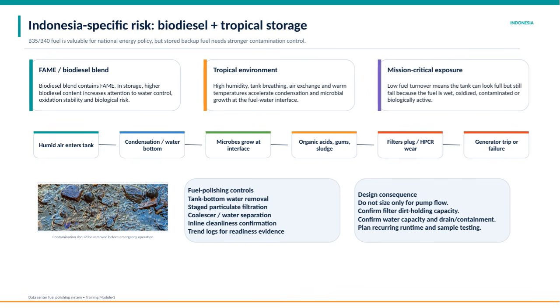When designing fuel systems for these conditions, it's important not to size equipment based only on pump flow. You need to confirm the dirt-holding capacity of filters, water handling and drainage capabilities, and plan for regular runtime and sample testing to maintain long-term fuel quality and system reliability.